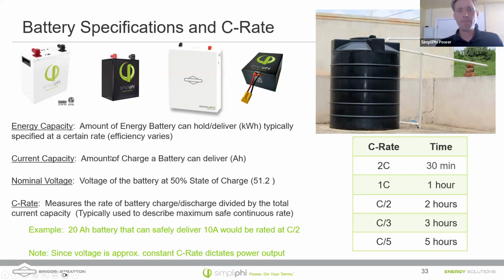Current capacity is the amount of charge a battery can deliver. Current times time gives you charge, in amp hours. So often our batteries have an amp hour rating. Our 48 volt Phi and AmpliPHI batteries have a 75 amp hour rating. What that means is they can deliver 37.5 amps for 2 hours, or 75 amp hours total. That doesn't vary. That isn't specified. That's a certain amount of charge.